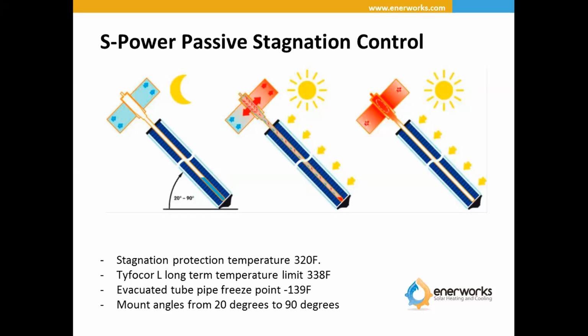Now, what happens with our stagnation method is the clever people in Germany designed it with a fluid and a vacuum that allows it to create a vapor lock if, for instance, you have no load. So if the temperature in the manifold gets to, it was 165 Celsius, which is, I think, about 350 degrees, at that point, you have a vapor lock. So it won't actually get any hotter than that, and essentially it stops producing energy. And this is the reason.